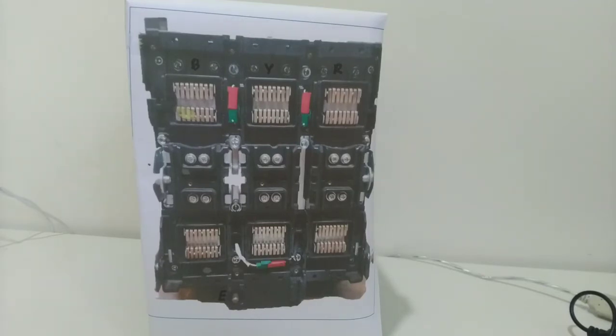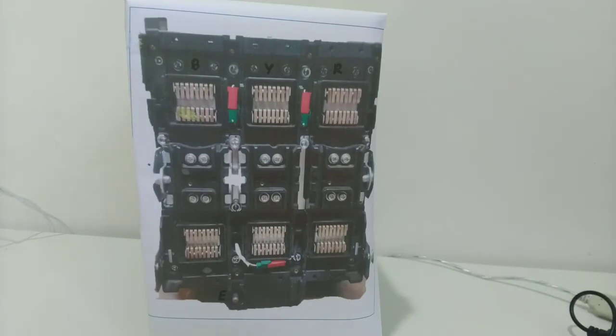In closed ACB position, we need to test for phase to phase and phase to earth terminal. Here are the phases and this is the earth. I already labeled the R, Y, B phase terminals. First, we need to check whether the ACB is in on or off condition. If it is off, we need to charge the ACB first and then turn it on.